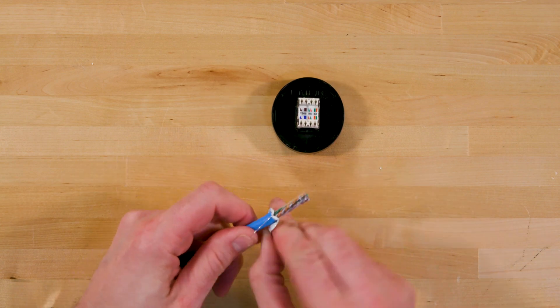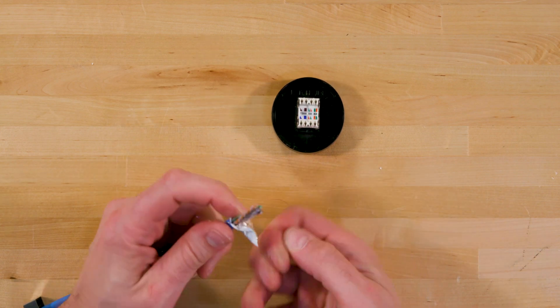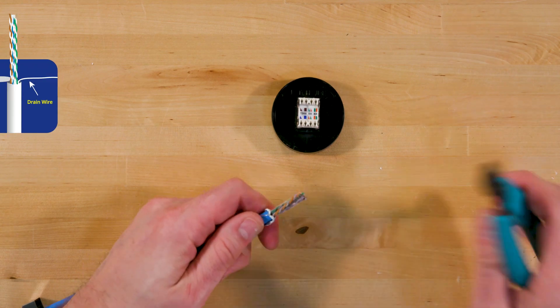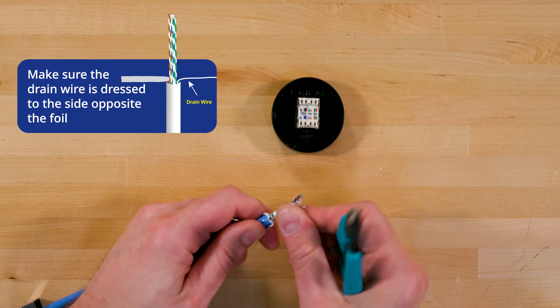Unwrap the foil from around the conductors. Fold it in half with the conductive side facing out and dress it to the side. Make sure the drain wire is dressed to the side opposite the foil.